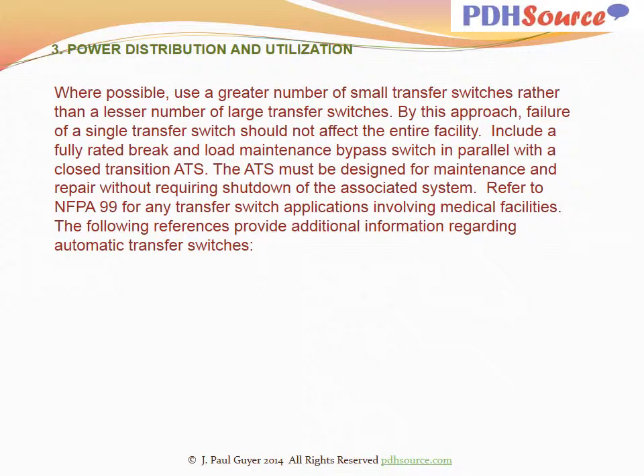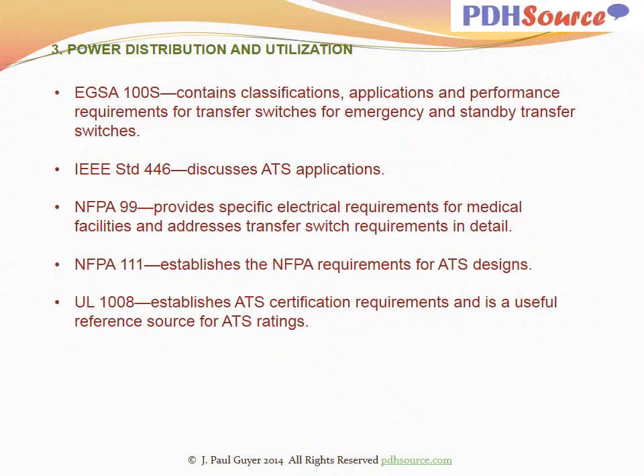The following references provide additional information regarding automatic transfer switches. EGSA 100S contains classifications, applications, and performance requirements for emergency and standby transfer switches. IEEE Standard 446 discusses ATS applications. NFPA 99 provides specific electrical requirements for medical facilities and addresses transfer switch requirements in detail. NFPA 111 establishes the NFPA requirements for ATS designs. UL 1008 establishes ATS certification requirements and is a useful reference source for ATS ratings.